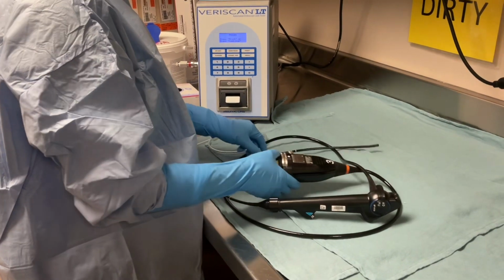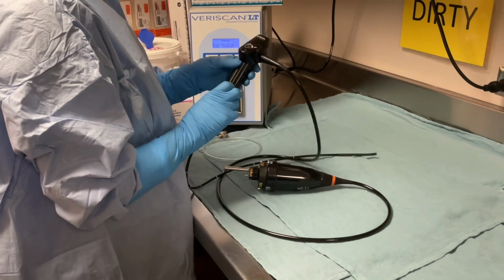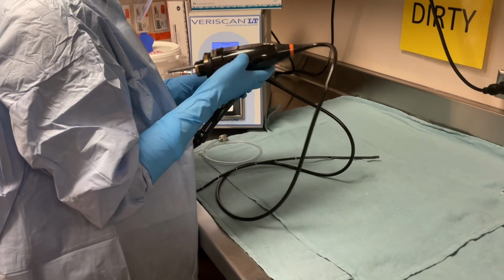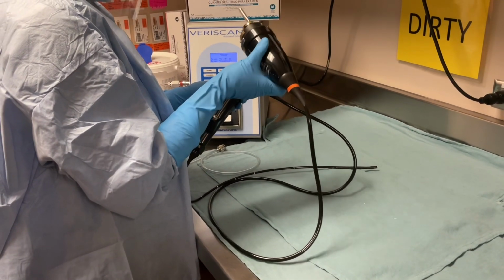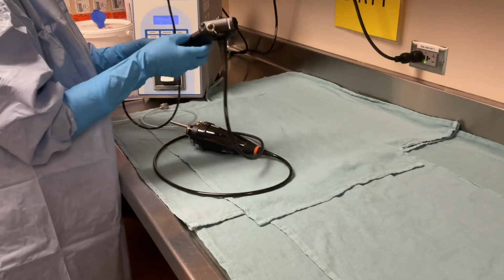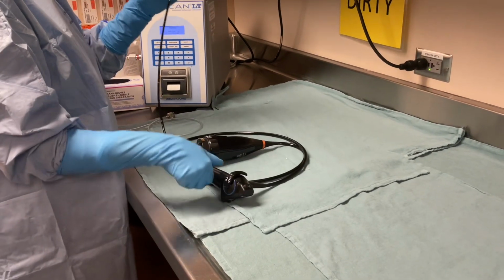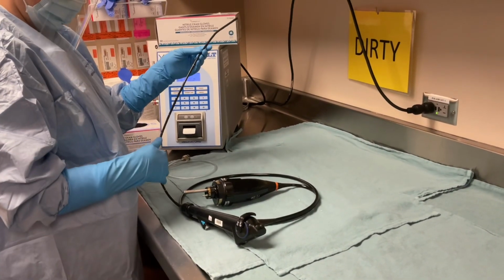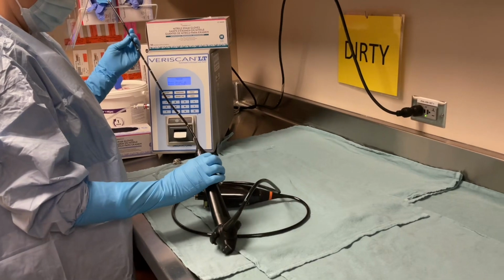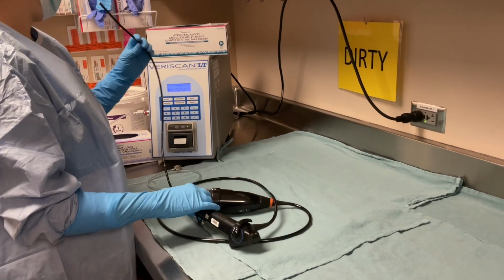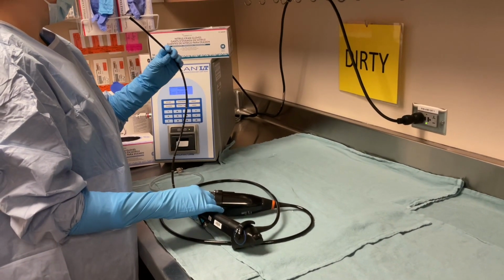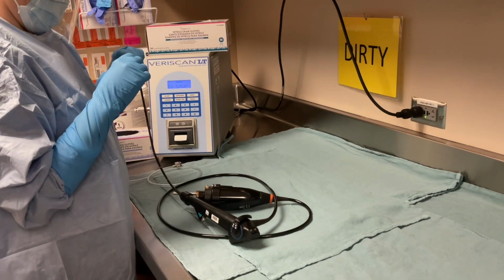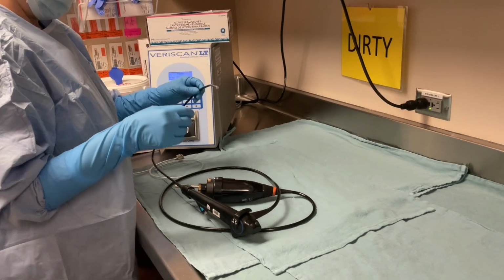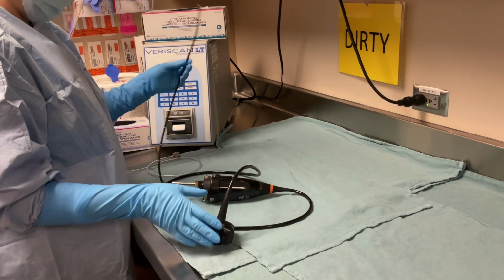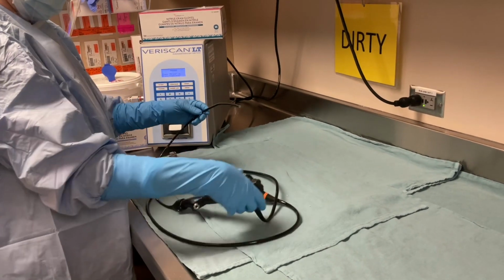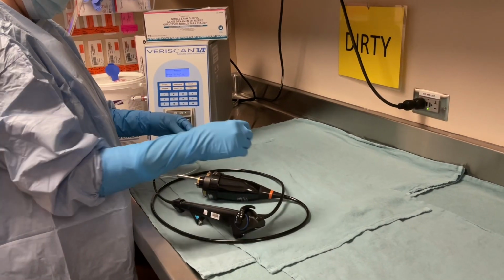Inspect the control section and endoscope connector for excessive scratching, deformation, loose parts, or other irregularities. Inspect the external surface of the entire insertion section, including the bending section and the distal end, for dents, bulges, swelling, scratches, peeling of coating, holes, sagging, transformation, bends, adhesion of foreign bodies, missing parts, protruding objects, or other irregularities.